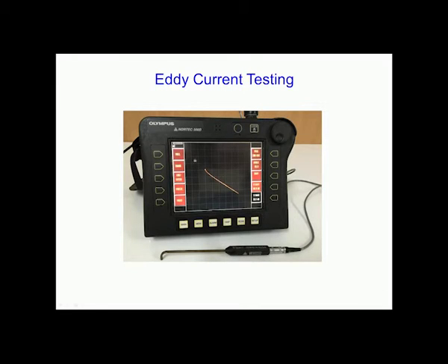And you could also see here there are so many press buttons, and there is a knob which will control different parameters corresponding to each of these buttons. With the help of these buttons and this knob, you can vary several parameters during the test. For example, you can select a particular frequency, you can change the phase angle of the eddy current and so on. So, these switch buttons are very easy to use, and as a system this is very easy to operate as such.